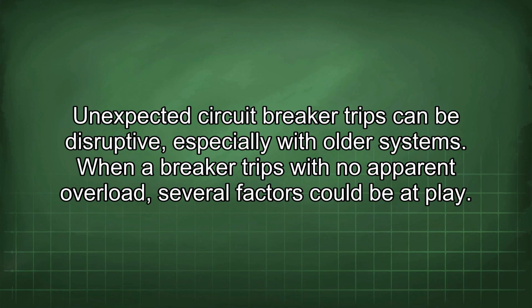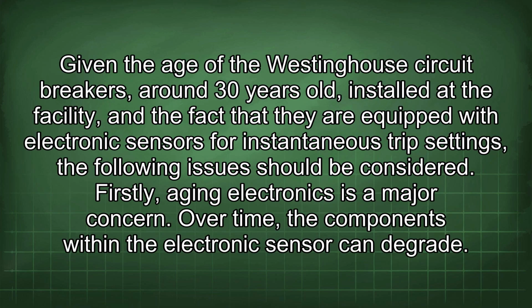Unexpected circuit breaker trips can be disruptive, especially with older systems. When a breaker trips with no apparent overload, several factors could be at play. Given the age of the Westinghouse circuit breakers, around 30 years old, installed at the facility, and the fact that they are equipped with electronic sensors for instantaneous trip settings, the following issues should be considered.